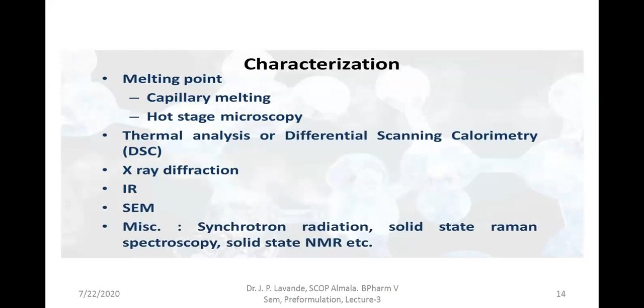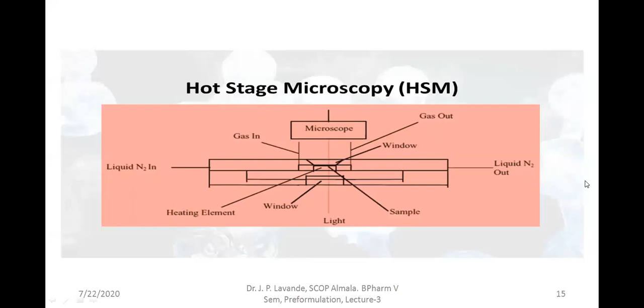As far as the hot stage microscopy is concerned, you can see this is the particular depiction of the hot stage microscopy. Here the sample is to be taken, and the sample is to be heated, and there is an entry of the gas from one side and an exit of the gas from the other side. That is the liquid nitrogen gas that is to be injected, and that is to be taken out. So this is the method which is said to be the hot stage microscopy, and the microscope is used in order to detect the melting point.